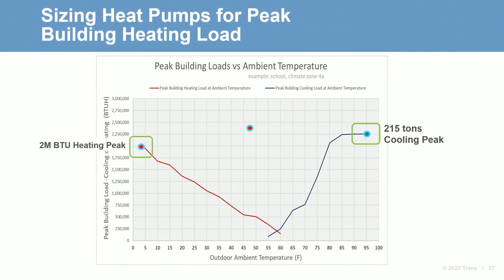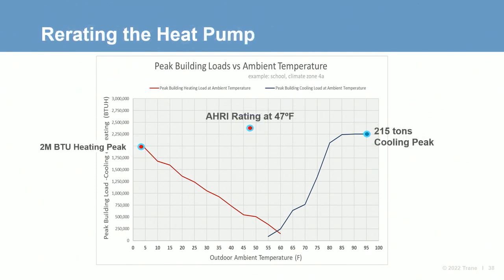If we size this plant for cooling and ran the air-to-water heat pumps at the AHRI rating condition of 47 degrees, it would appear that we have more than enough capacity to meet the heating peak. However, that nominal rating point means very little in regards to this specific project. For this example, we need to find the performance of the heat pump at 4 degrees. Re-rating the heat pump at the project design conditions shows us we'd run out of heating capacity around 15 degrees.